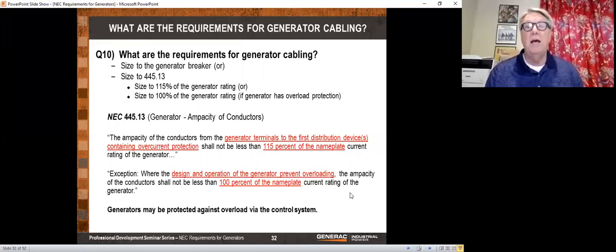Well, if you size according to 100% of the generator rating, then you can use two 500 MCM cables rated 380 amps a piece. So that gives you 760 amps, which is more than the 752 that is the rating of the generator. If you go with the circuit breaker, now you can't do that. You're going to have to go with either larger wire, and I've always assumed that if I use anything higher than 500 MCM, the contractor's going to kill me. Or you're going to have to go with another conduit, another set of wires. So this can save you a significant amount of money, and the copper prices are not ever going to go down. They continue to go up. So I recommend sizing to 100% of the generator rating typically.